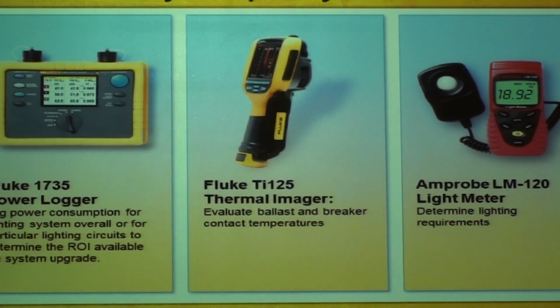To identify waste on lighting systems, again look for power quality issues to make sure you have proper power supply, use a thermal imaging camera to look at the ballasts and breaker temperatures, and it's very important to have a light meter, because a light meter or lux meter is used to measure the candles or lux lumens, to check if a room is adequately lighted.